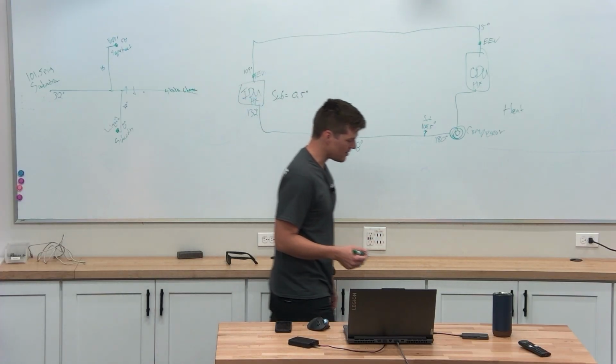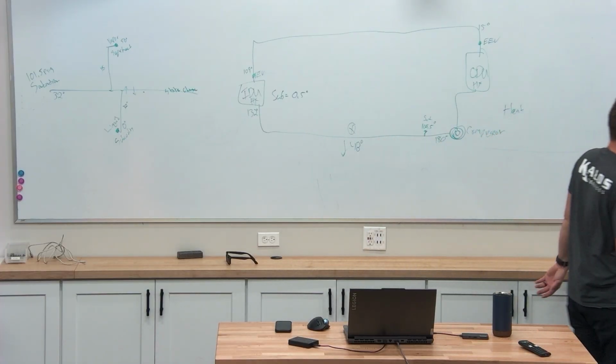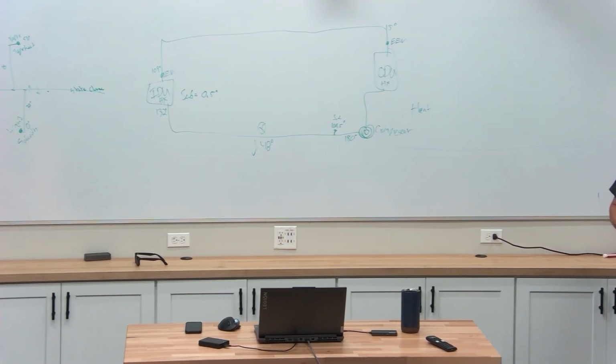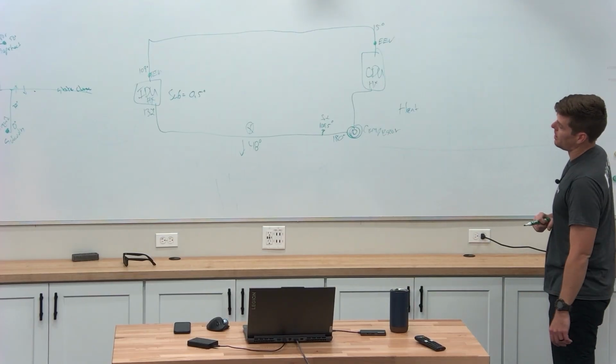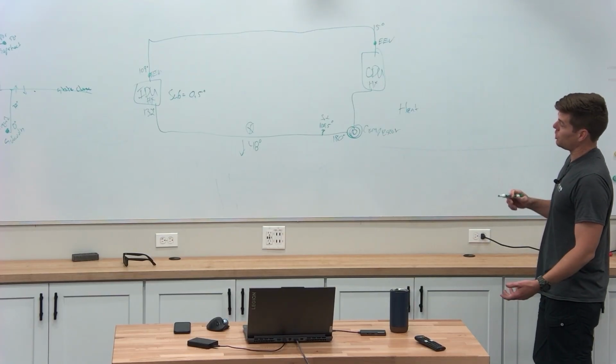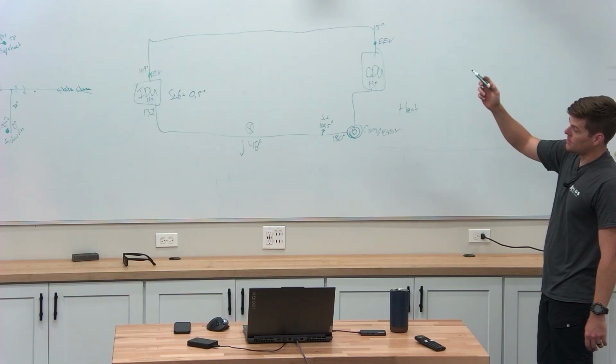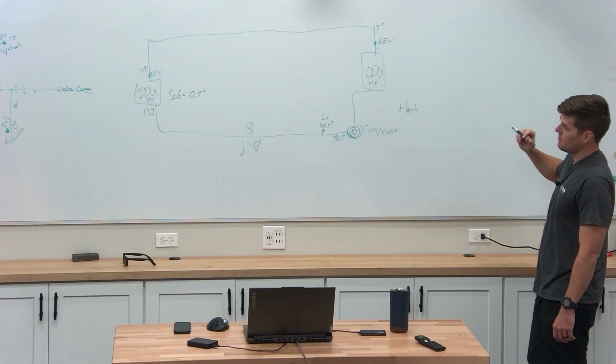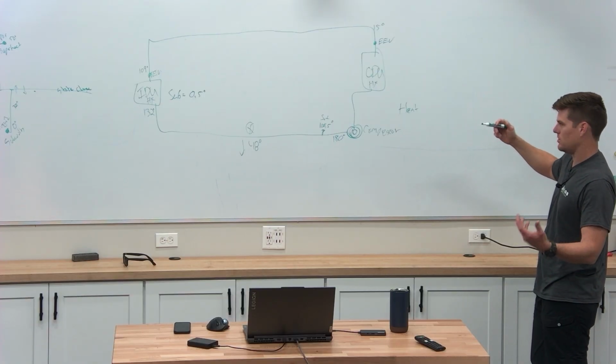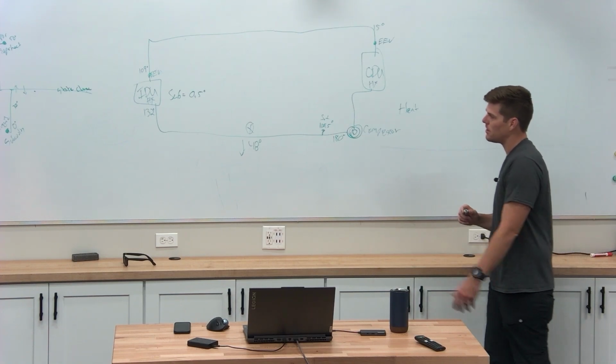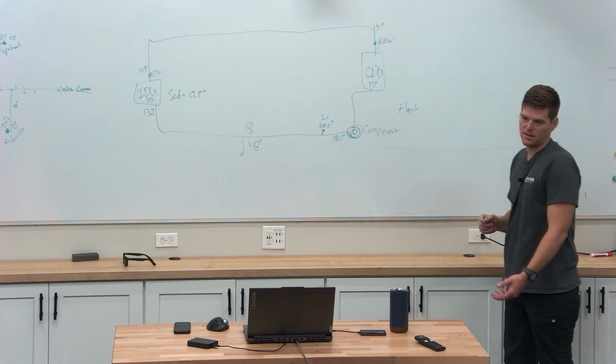It's 15 degrees. Man, there must be like this giant subcooler between here and here, right? It's our outdoor. So then you start asking the questions of, okay, well, that's a huge temperature drop, right? If we're losing a ton of heat between here and here, maybe it's just really subcooled. You're just going through a bunch of water. They ran the line set through a lake by accident. It happens.